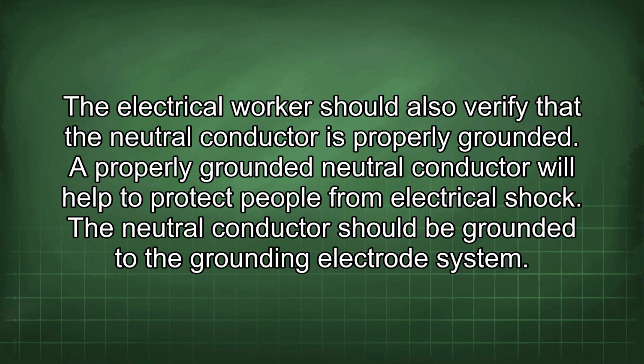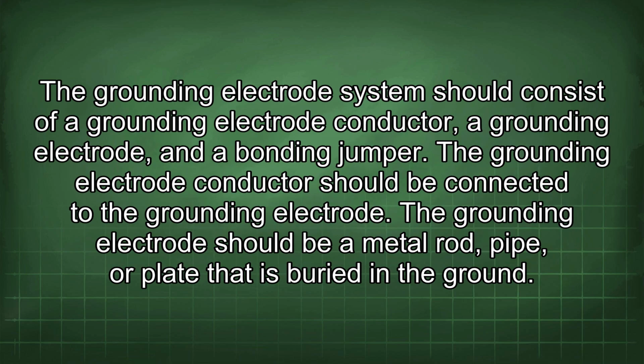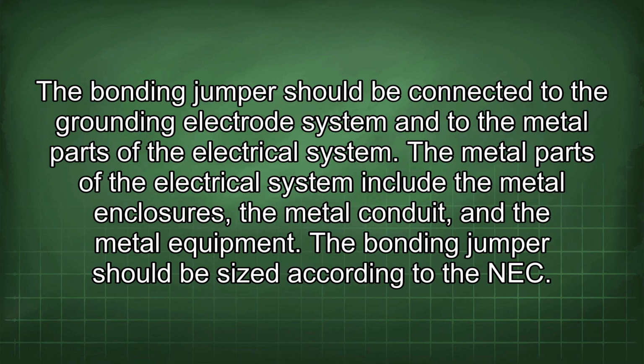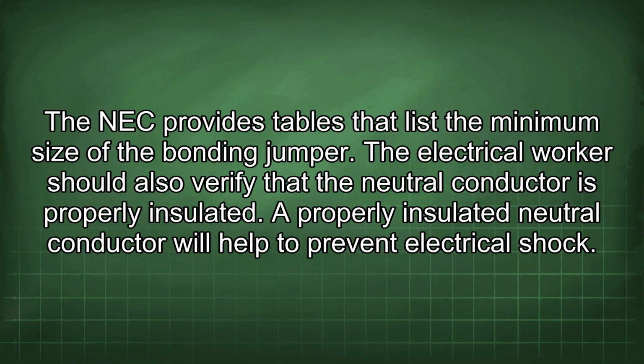The neutral conductor should be grounded to the grounding electrode system. The grounding electrode system should consist of a grounding electrode conductor, a grounding electrode, and a bonding jumper. The grounding electrode conductor should be connected to the grounding electrode. The grounding electrode should be a metal rod, pipe, or plate that is buried in the ground. The bonding jumper should be connected to the grounding electrode system and to the metal parts of the electrical system. The metal parts of the electrical system include the metal enclosures, the metal conduit, and the metal equipment. The bonding jumper should be sized according to the NEC. The NEC provides tables that list the minimum size of the bonding jumper.